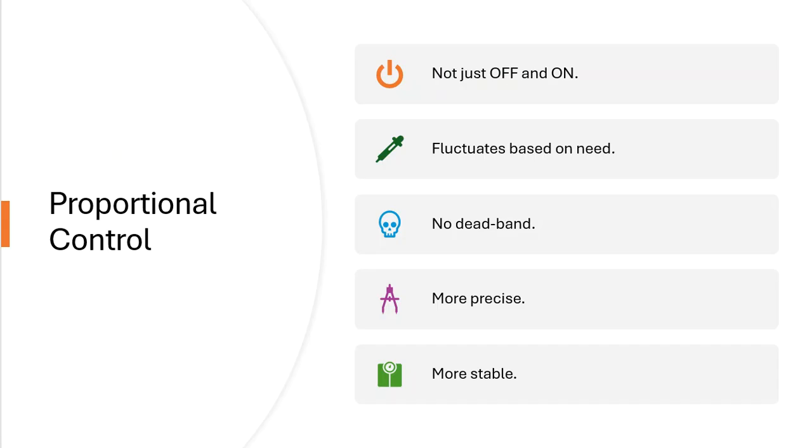So it's not a big deal, and it actually is a good deal, because with proportional control it is not fluctuating as much. With the on and off situation, we want to give it some time. We don't want things to start up every couple of minutes because, again, that could damage the instrument or the pieces and parts that make it work. So proportional control is kind of constantly on. It's not fully turning itself off, and it's not fully turning itself on. It is slowing things down tremendously or speeding things up in order to get what it needs.